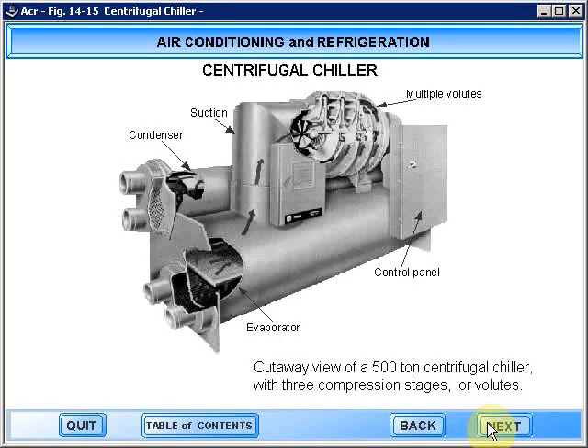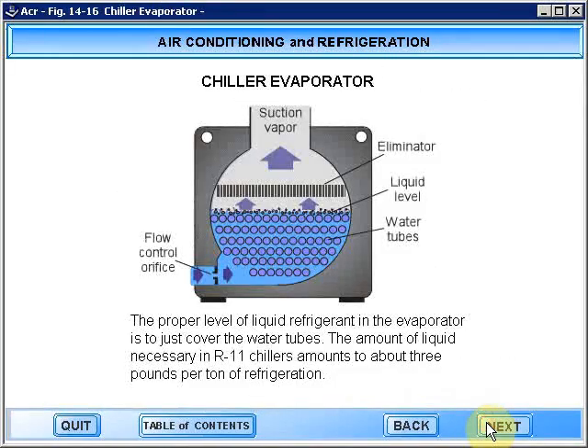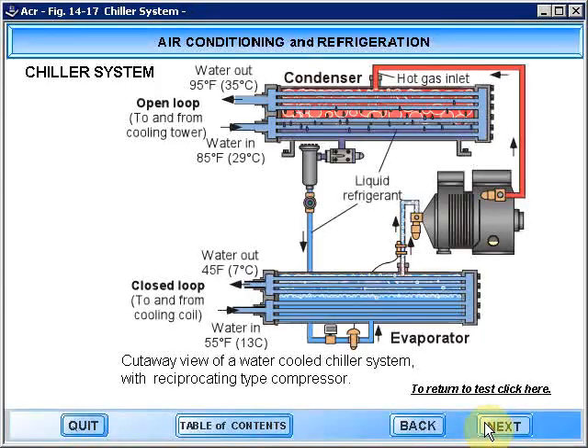This is a cutaway view of a 500-ton centrifugal chiller with 3 compression stages, or volutes. The proper level of liquid refrigerant in the evaporator is to just cover the water tubes. The amount of liquid necessary in R11 chillers amounts to about 3 pounds per ton of refrigeration. This is a cutaway view of a water-cooled chiller system with reciprocating type compressor.